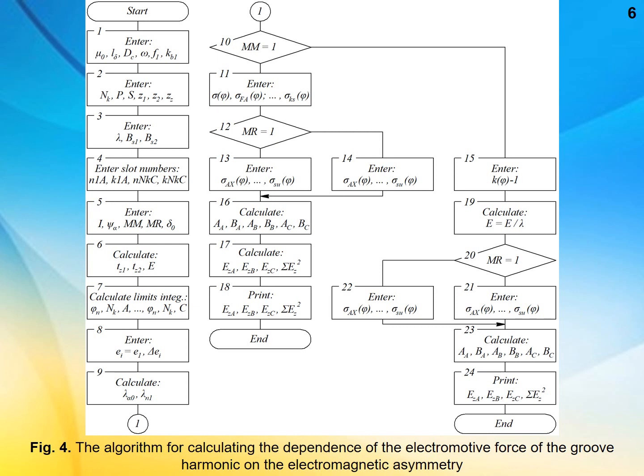The dependence of the electromotive force of the groove harmonic of individual phases and the sum of the squares of the amplitudes on the electromagnetic asymmetry was calculated on an electronic computer. Figure 4. The developed technique makes it possible to determine the levels of groove harmonic components in the phase windings of electric machines. Depending on the connection scheme of the asynchronous motor winding, star or delta, the scheme and the load of the electrical network, these harmonics spread over the electrical network, creating current harmonics or voltage harmonics.